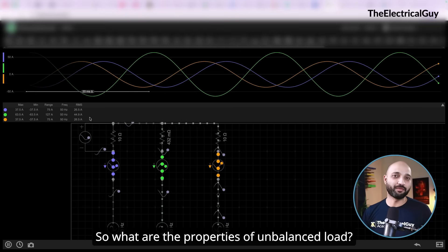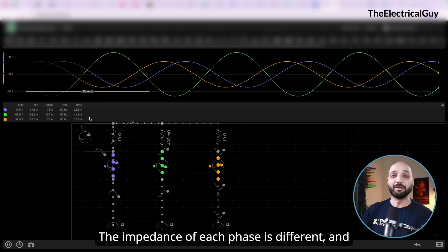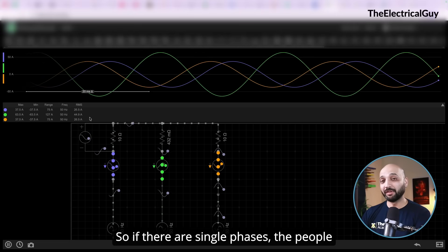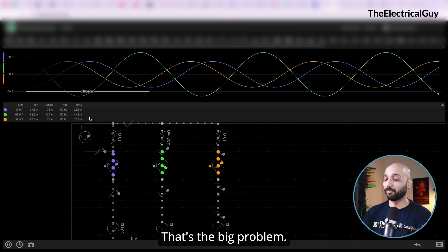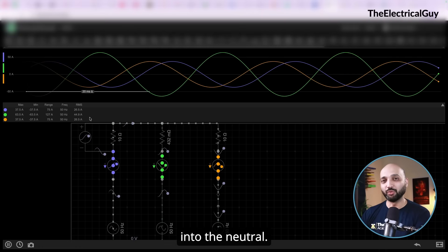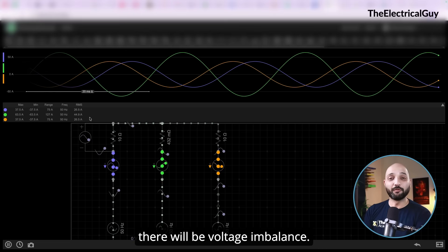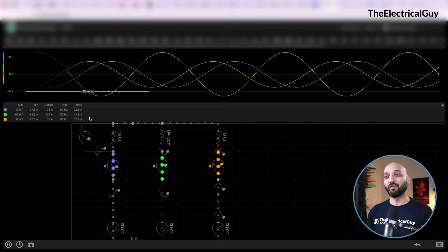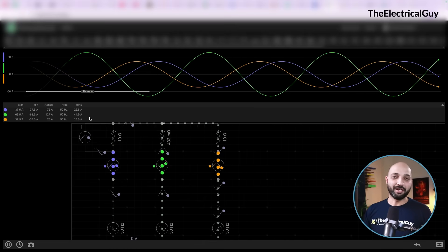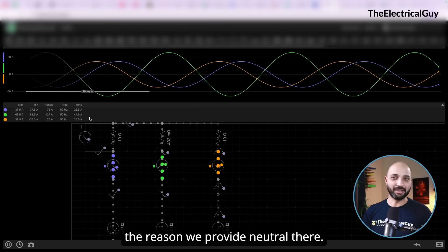The properties of an unbalanced load are: first, the current flowing through the phases is different, not identical; second, the impedance of each phase is different, which results in different currents; third, the voltage drop is unequal — so single-phase consumers will receive unequal voltages; fourth, the waveform is disturbed; and most importantly, there will be current flowing into the neutral. If you remove the neutral from the circuit there will be voltage imbalance. That is why a neutral wire is provided in the distribution side of the power system.